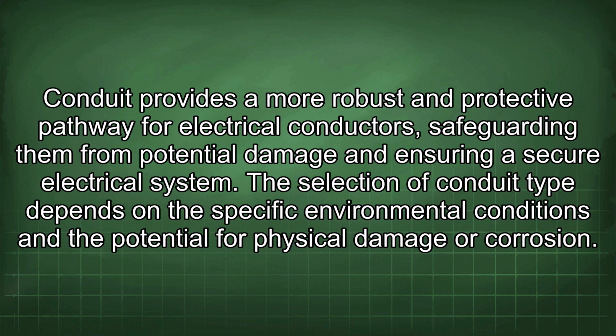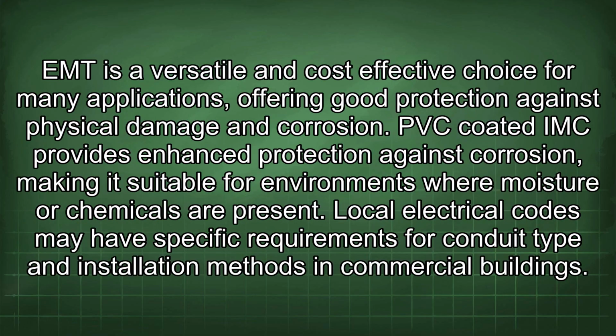The selection of conduit type depends on the specific environmental conditions and the potential for physical damage or corrosion. EMT is a versatile and cost-effective choice for many applications, offering good protection against physical damage and corrosion. PVC-coated IMC provides enhanced protection against corrosion, making it suitable for environments where moisture or chemicals are present.